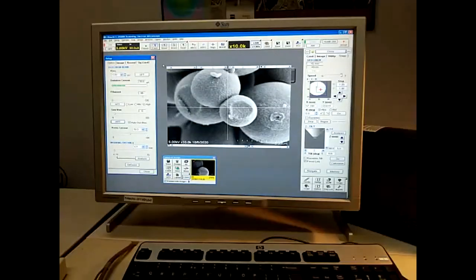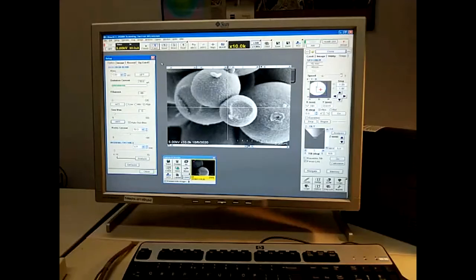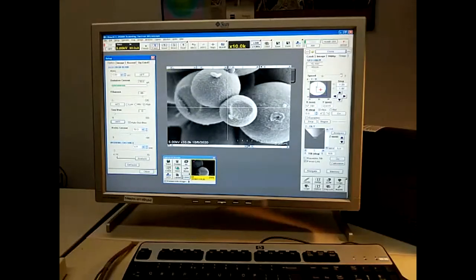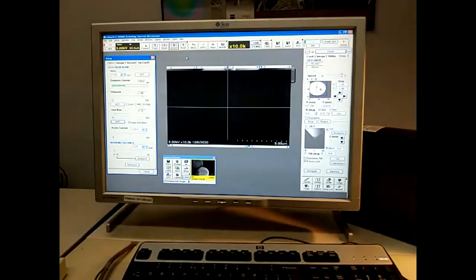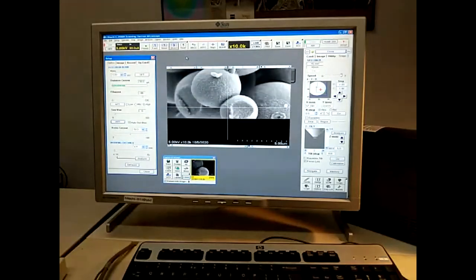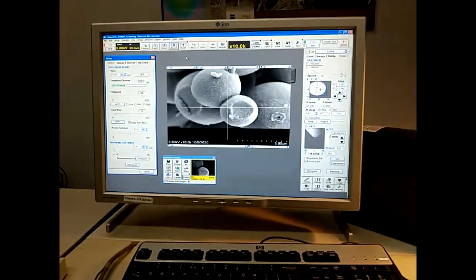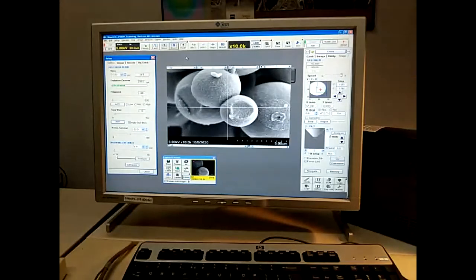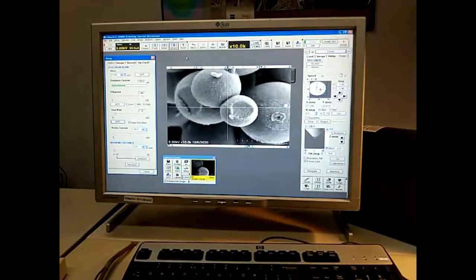Here we have it at 5 kV with a probe current setting of 50 at 10,000 times magnification on fast mode. At slow mode I'm working quite closely to the beam at this point. So you're going to see some depth of focus issues with the focus dropping off in the beads that are further away from the beam point.